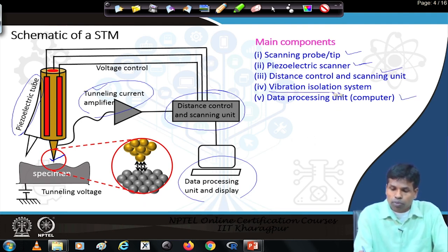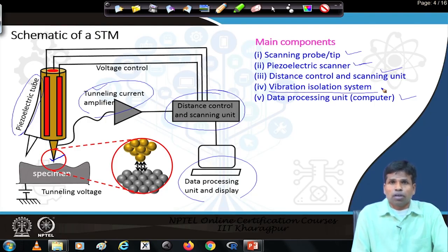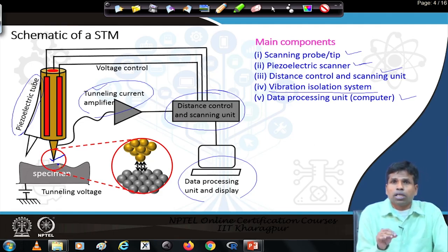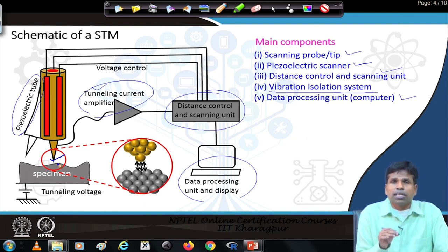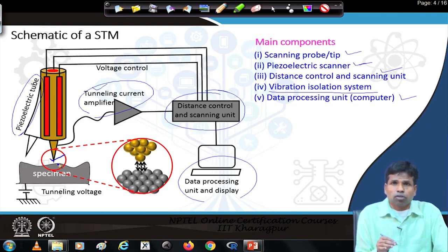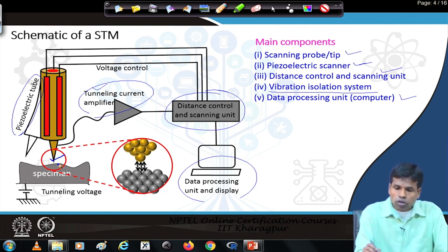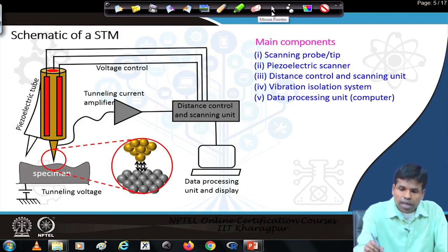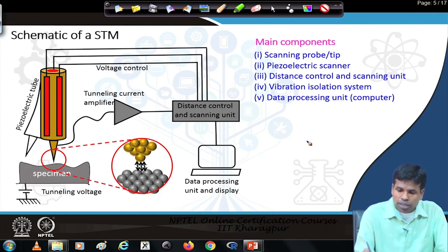Another important requirement for this microscope is a vibration isolation system, because the tip-to-specimen distance or gap is less than 1 nanometer — very small. Therefore, any small vibration is not acceptable; it should be completely vibration free. Only then will we be able to get precise and accurate data of the specimen surface. We will now discuss each component of the scanning tunneling microscope.